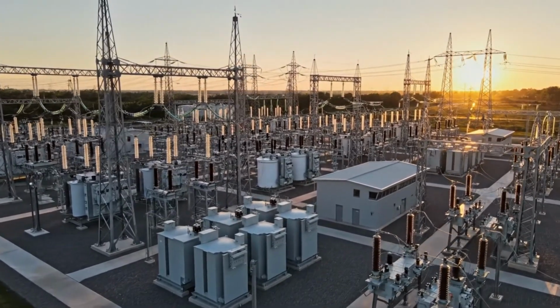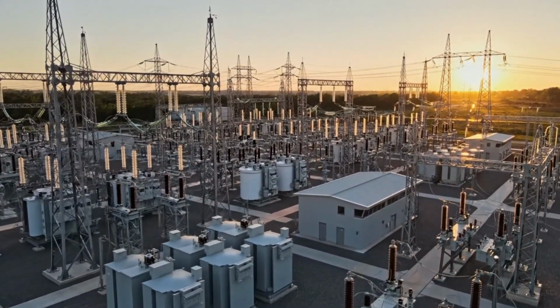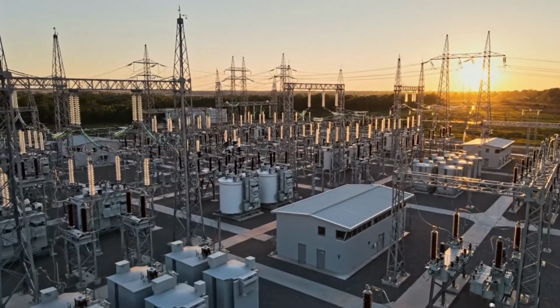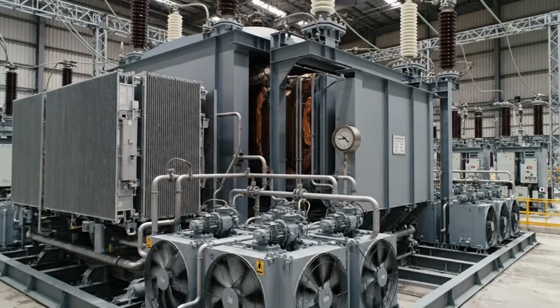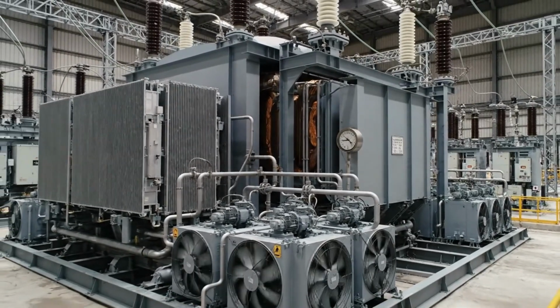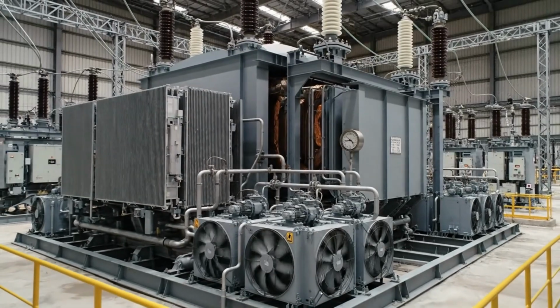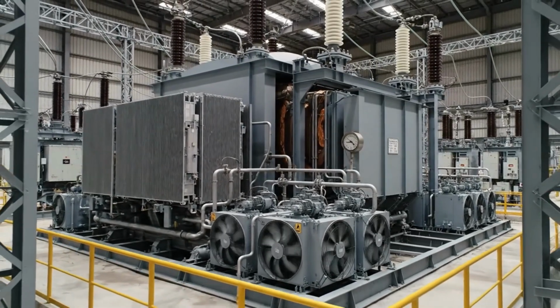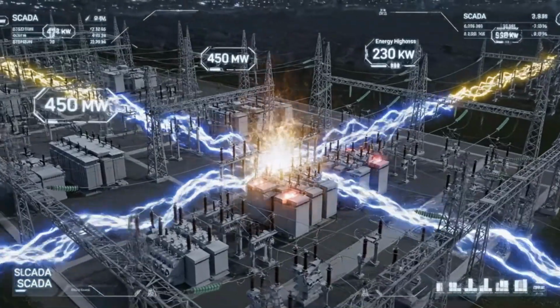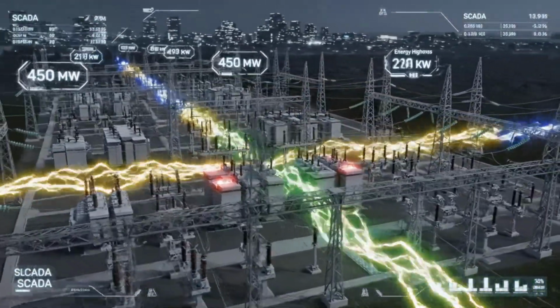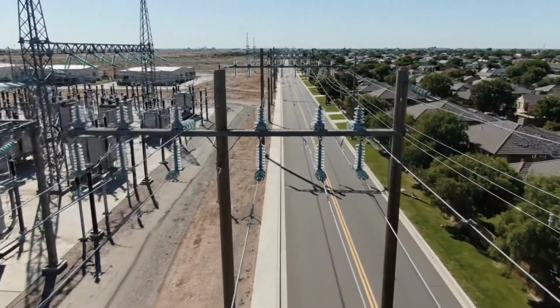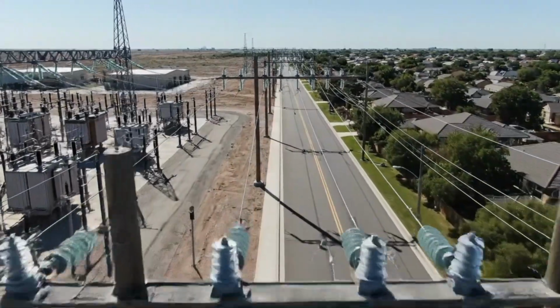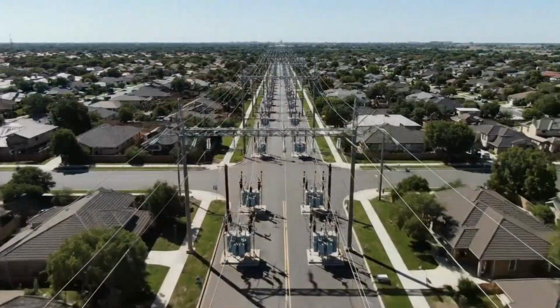Major substations are the heart of the transmission system. This substation interconnects 5 lines. Step-down transformers at major substations reduce transmission voltage to distribution voltages suitable for regional networks. Inside this substation, power flows following the path of least electrical resistance. From the transmission substation, distribution feeders carry power toward neighborhoods.